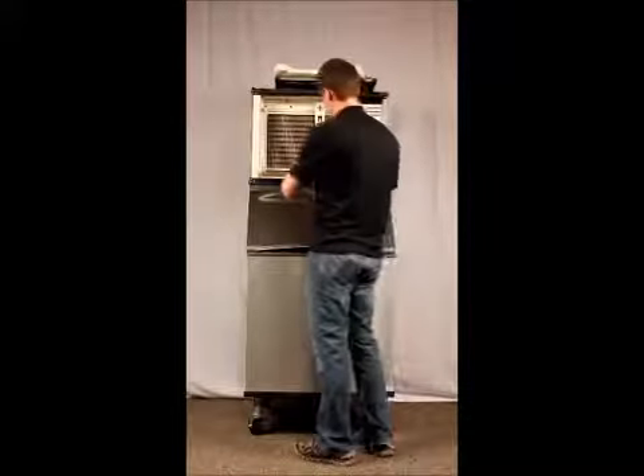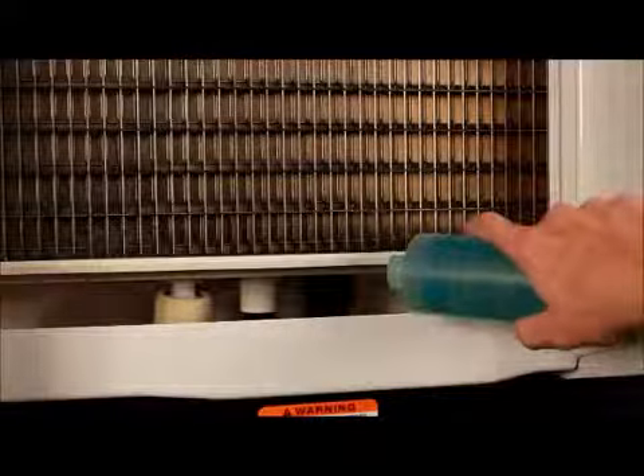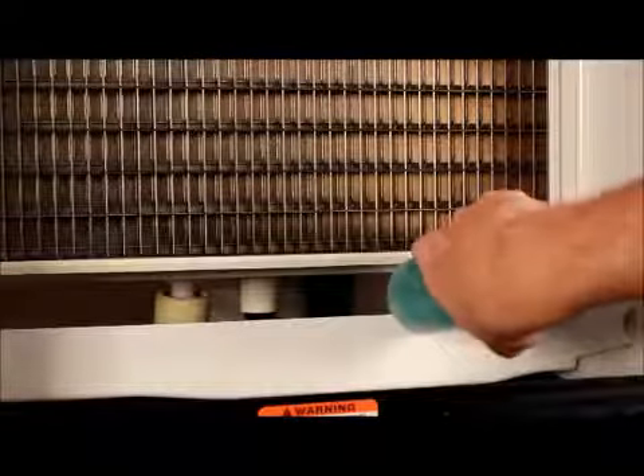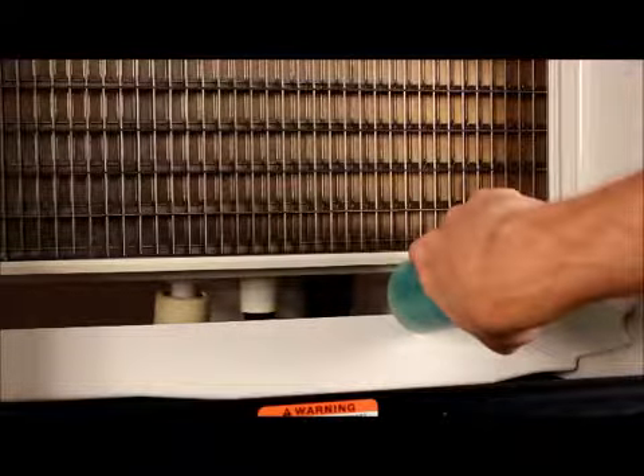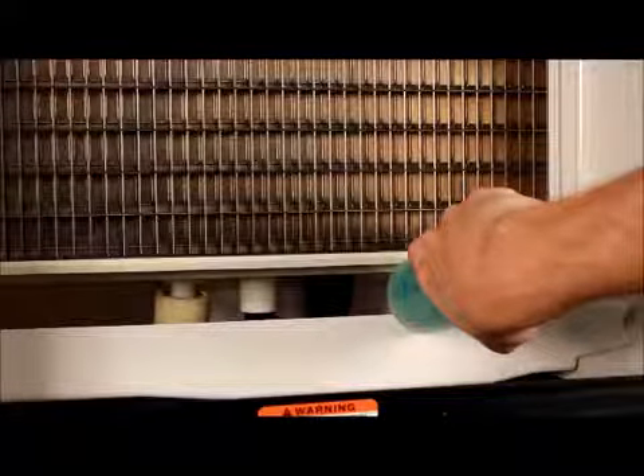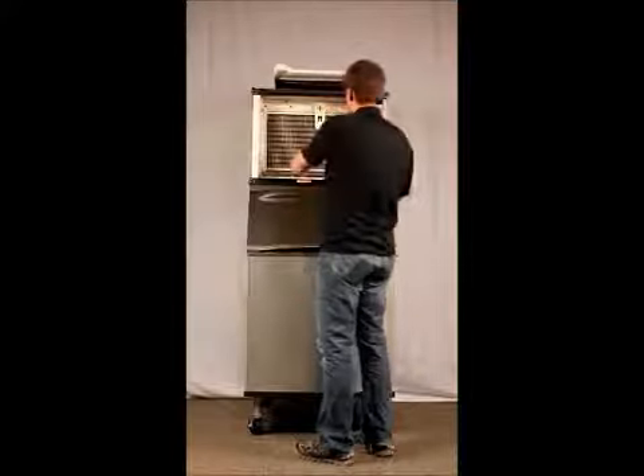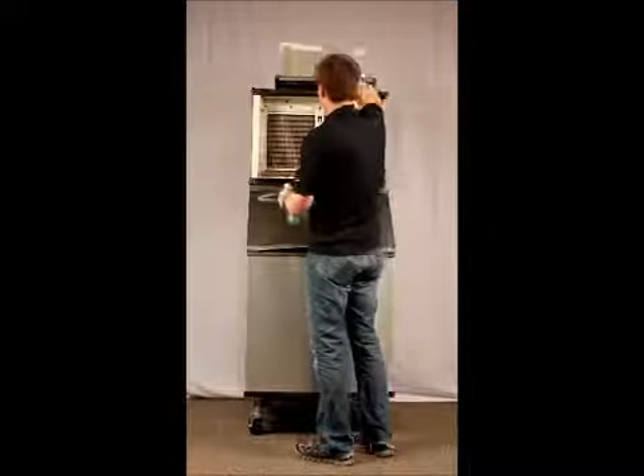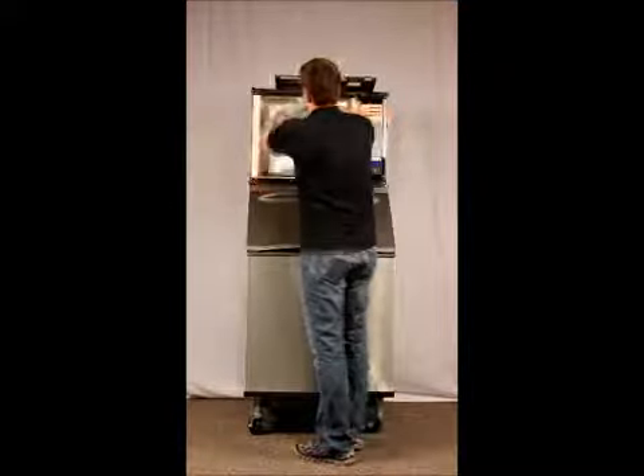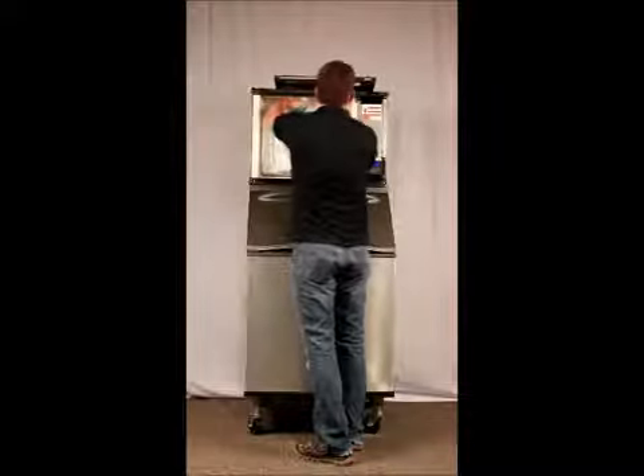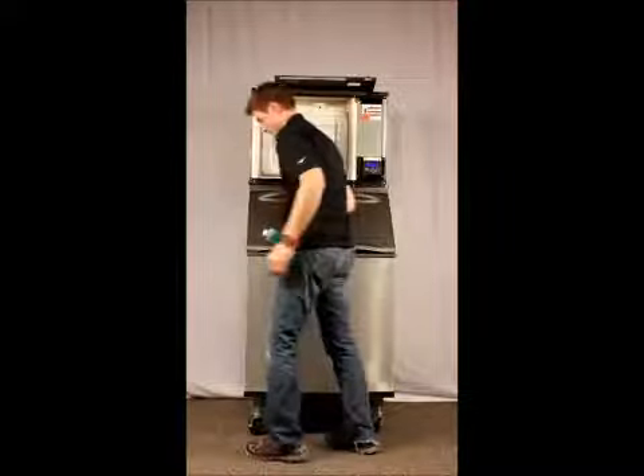You will also notice that at this point there is the option for the ice machine to return automatically to making ice again once the cleaning cycle is complete. If the intention is to only clean the water system, then it would be appropriate to do this at this time. If you plan to clean the other food service parts as well as sanitizing, then do not select this option at this time.